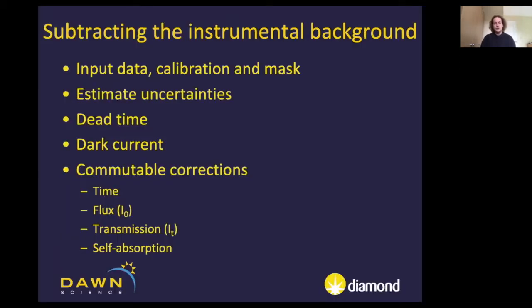Once data is input, the first step is to estimate uncertainties by calculating Poisson statistics on each pixel for photon counting detectors. We then correct for detector dead time using values provided by the detector manufacturer — for us, Dectris. The dark current, a measure of background radiation hitting the detector, is less of a concern for synchrotrons where count rates are high and exposures are short — typically one second or less — but becomes significant for lab instruments measuring for 10 to 40 minutes or even hours.